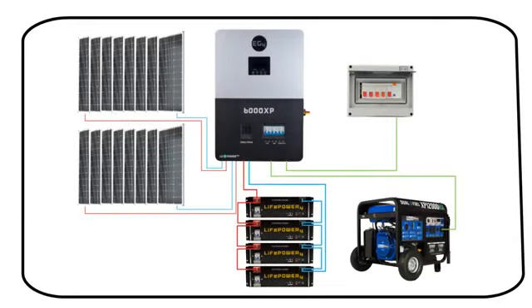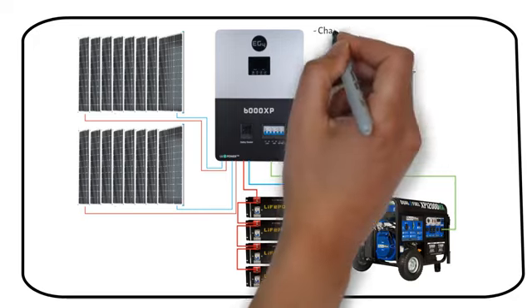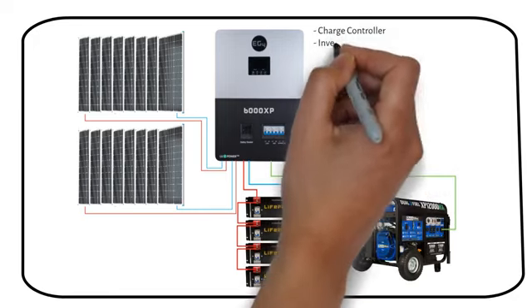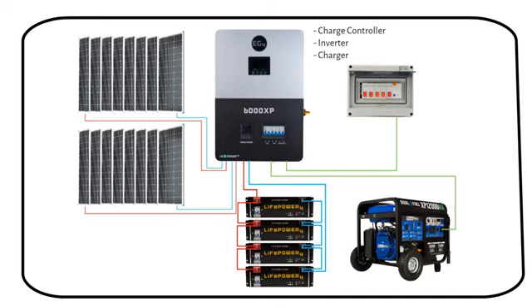This system uses a hybrid inverter. A hybrid inverter is a combination of a charge controller, inverter, and a charger. It's also called an all-in-one system. Advantages are reduced wiring and easier setup. However, the drawback is more idle consumption. This means the hybrid inverter will draw more power from the batteries just to be on. You must keep this in mind when you make your load calculation.